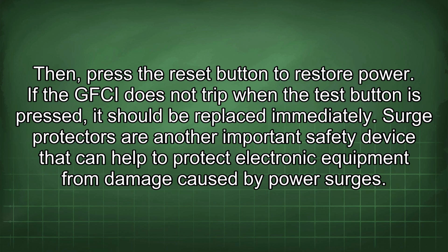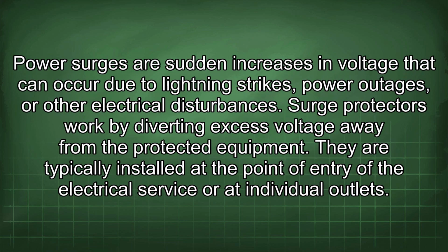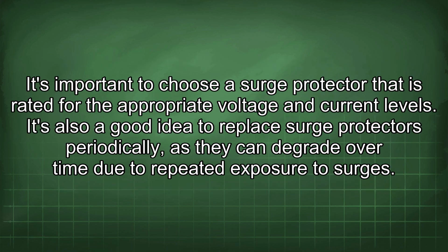Surge protectors are another important safety device that can help to protect electronic equipment from damage caused by power surges. Power surges are sudden increases in voltage that can occur due to lightning strikes, power outages, or other electrical disturbances. Surge protectors work by diverting excess voltage away from the protected equipment. They are typically installed at the point of entry of the electrical service or at individual outlets. It's important to choose a surge protector that is rated for the appropriate voltage and current levels. It's also a good idea to replace surge protectors periodically, as they can degrade over time due to repeated exposure to surges.